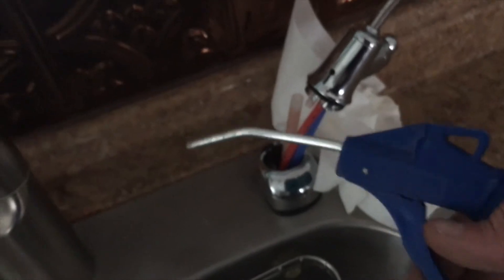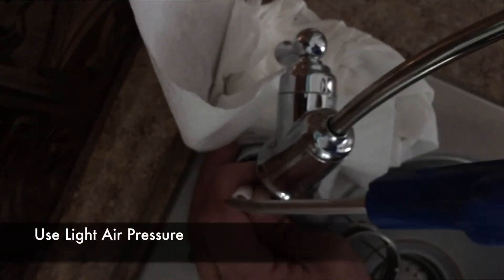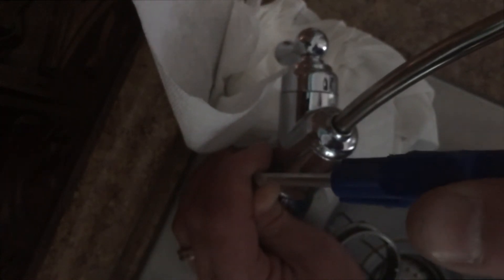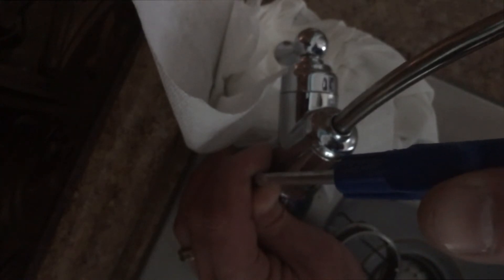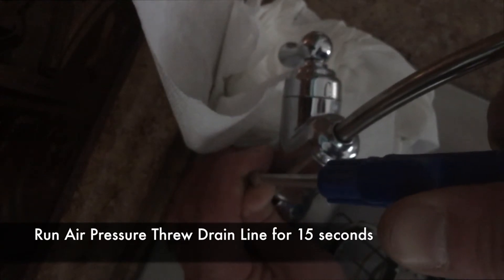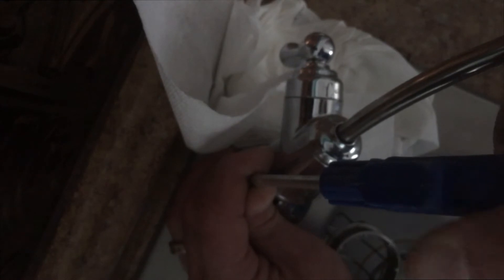See all this red stuff? That's all the sediment and dirt this thing's been washing out — and now it's clogged. What I'm going to do is take an air compressor blowgun and stick it in there. Keep your face away from the drain and apply light pressure. Once you hear all the clumps stop hitting the drain, you're done.